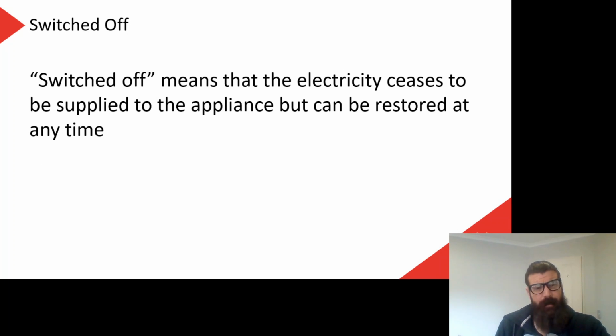Switched off has a slightly different meaning. It means the electricity ceases to be supplied to the appliance but can be restored at any time. So the difference between isolated and switched off is, if I switch off a circuit breaker or a light switch or something like that, that's switched off. There's no electricity present in that circuit at that time. But if I only switch it off, then somebody could come and turn that back on easily, or I could turn that back on.